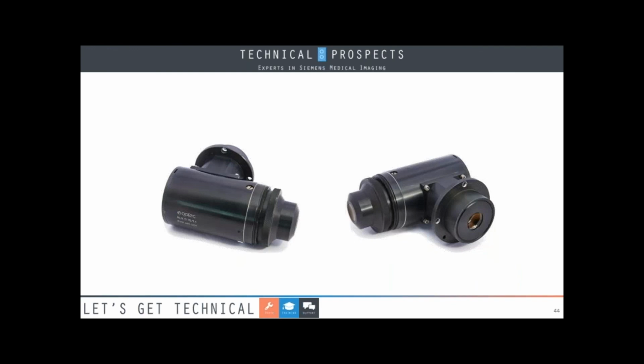Okay. Now, if you have a problem with an image intensifier, you're going to want to isolate the issue. You're going to want to use a mirror to see if you have a bluish light coming into this camera that's mounted on top of that image intensifier. And yeah, that's actually just a regular camera. It's expensive. Those things are about $10,000, so they're not a standard Kodak or anything, but it's a standard camera. And I was really shocked to see that they actually just wear out, even though all I see is a lens that focuses. But I had them wear out. But you're going to want to see if you have a little bit of bluish light coming out of there.